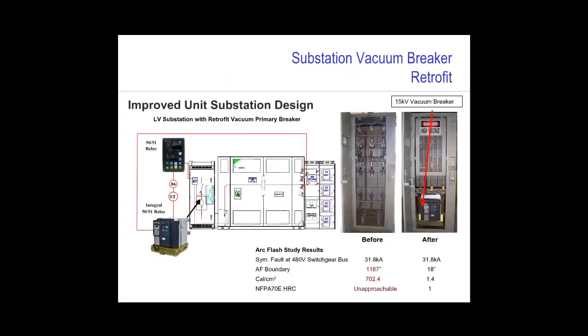So this brings us back to our earlier example of an integrated paper mill in the Pacific Northwest of the U.S. You remember in this case, because there was no secondary main breaker in the substation, after the site conducted an arc flash study, they found that racking a breaker off of the secondary bus was a very dangerous situation. In fact, the calculations from the NFPA 70E showed that it was unapproachable, or there was no protective equipment a service personnel could wear and be safe.